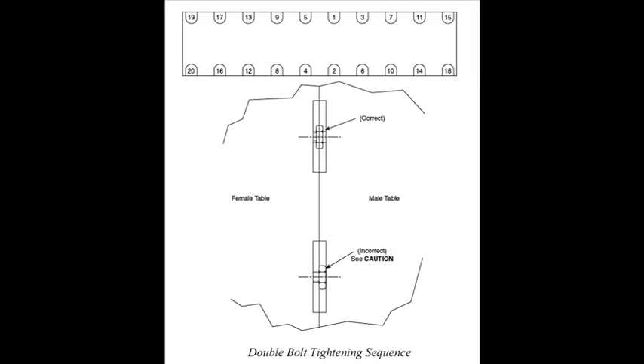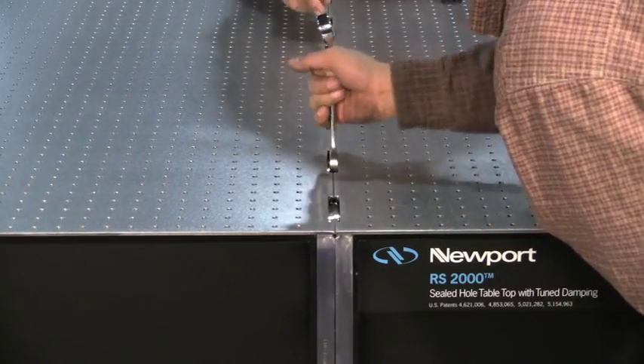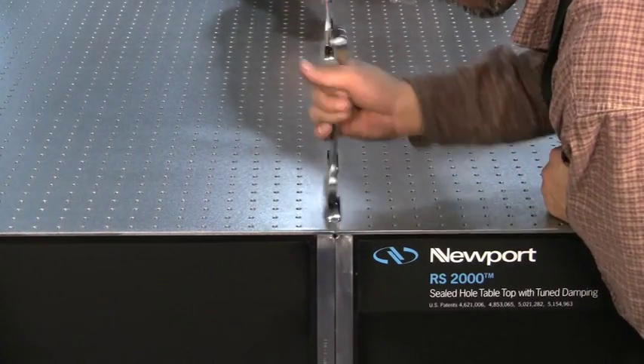After all the bolts are uniformly engaged and the table sections are in full contact, use the recommended staggered tightening sequence to apply final torque of 60 foot-pounds to all bolts. This sequence helps ensure uniform torque loading and proper mating of the plate. It is important that this sequence be followed carefully.